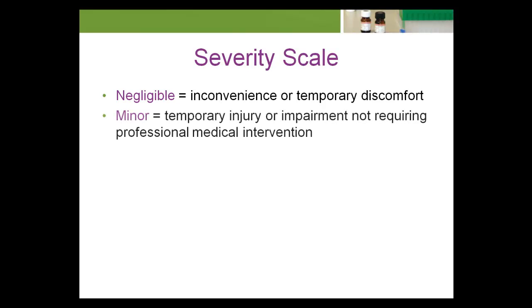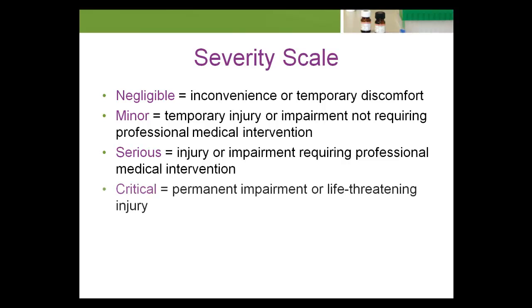EP23A provides an example of a severity scale using five descriptive categories: negligible equals inconvenience or temporary discomfort; minor equals temporary injury or impairment not requiring professional medical intervention; serious equals injury or impairment requiring professional medical intervention; critical equals permanent impairment or life-threatening injury; catastrophic equals patient death.